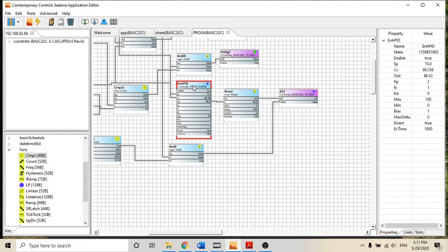And I think that also has to do with my integral value perhaps, which I can set to 0, and we can go with just proportional gain. That would be a lot easier to see. In that case, right now our out would only be 72. I'm going to take it out again, and we are going to see, now we're actually on heating mode, but I'm going to take it out again.